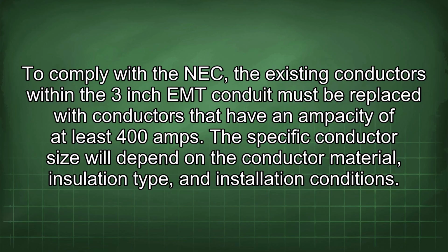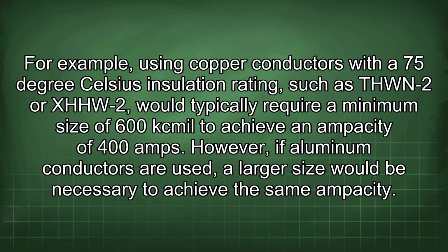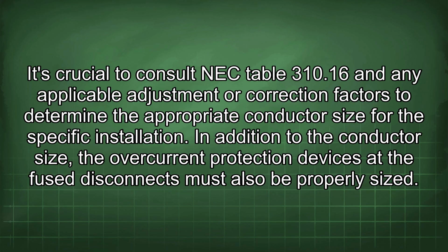The specific conductor size will depend on the conductor material, insulation type, and installation conditions. For example, using copper conductors with a 75 degrees Celsius insulation rating such as THWN-2 or XHHW-2 would typically require a minimum size of 600 kcmil to achieve an ampacity of 400 amps. However, if aluminum conductors are used, a larger size would be necessary to achieve the same ampacity.